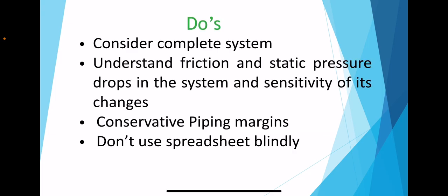So what are the do's for pump calculation? The calculation should consider the entire system, which means do not stop at the battery limit pressures. The friction and static pressure drops in the system and the sensitivity of its changes need to be understood.